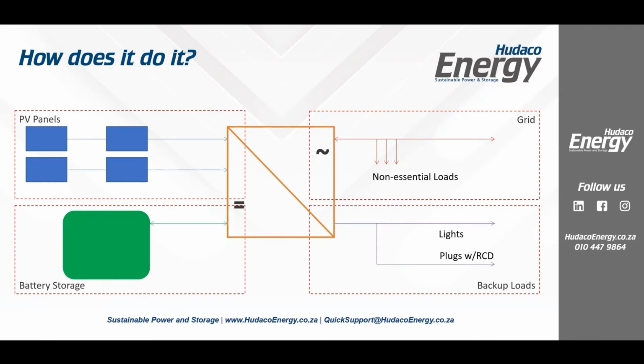All right. Do we have any questions on this architecture? It's a little bit different way of thinking when we compare to what's in the market at the moment, but it's extremely, extremely powerful. We have 13 kilowatt peak. We have a 13 kVA feed here, and the 6 kVA really only applies to the power that we can produce for the backup loads. We can actually support more than that. So if we were pulling 6 kVA from the batteries, for example, and we were running 4 or 5 kVA here, we could, if we were producing more from our PV panels, also feed all of these. We can do all of this at the same time. We can charge the batteries, we can run the backup loads, and we can run non-essential loads all at the same time. Good, so you have a question?